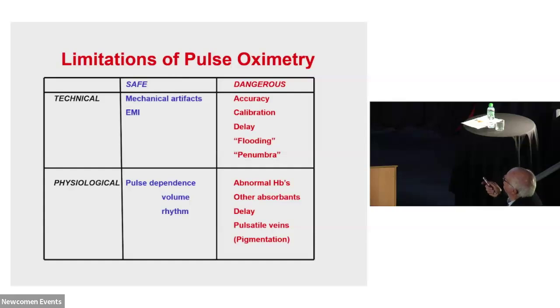If you can see that and it's wrong, obviously you know to think either it's a technical problem, mechanical artifacts, EMI, electro-interference, or it's physiological because the thing's pulse dependent. And if you can see that pulsatile trace, then the volume and the rhythm are correct. If they're not there, then you know that you're not getting the right results, and it's quite safe. Dangerous ones are where the thing looks as though it's working, and it's either not working and is dangerous.